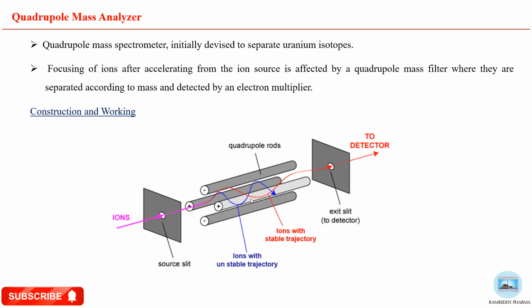Each and every ion has some electric charge. When they enter the quadrupole mass analyzer, they oscillate. Each ion passing through the quadrupole mass analyzer oscillates in this quadrupole electric field. First, we have to select one oscillating frequency. Each ion has its own oscillating frequency, so we can select the suitable oscillating frequency.